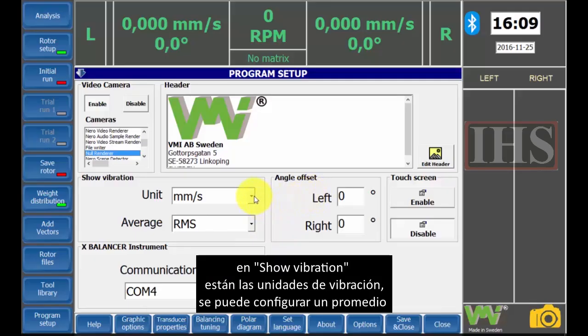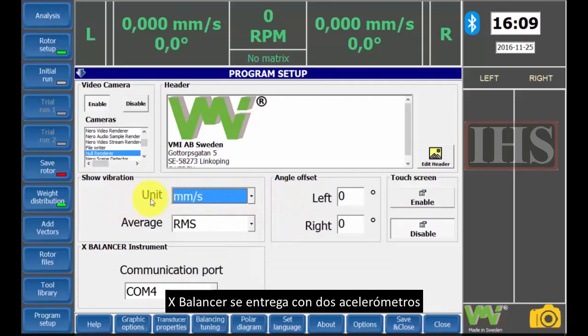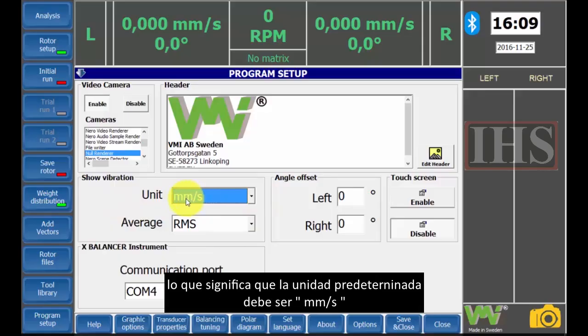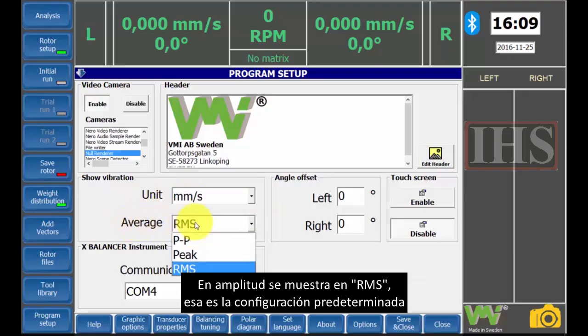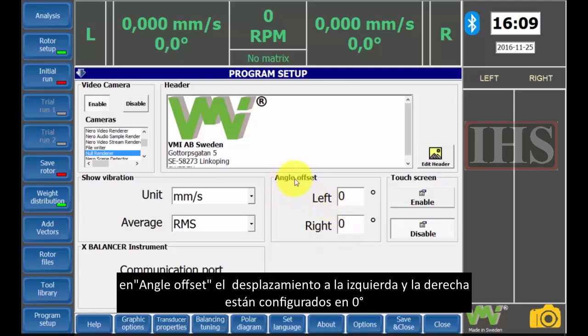Under Show Vibration, unit and average can be set. The X balancer is delivered with two accelerometers, which means that the default unit should be millimeters per second. The amplitude is shown in RMS, and that's the default setting. Under Angle Offset, the left and right are set to 0 degrees.